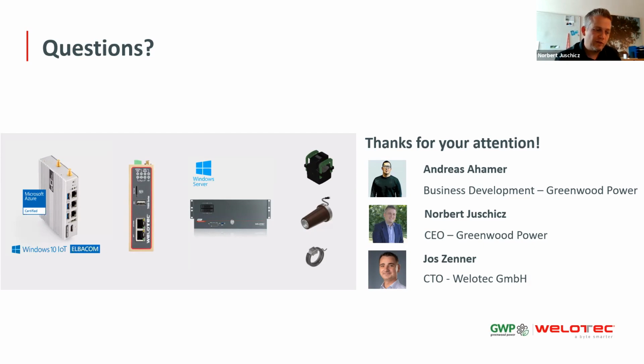If we go down to the low voltage area, it might make more sense, to be honest, because on the low voltage side the biggest use case is load management. In this case, you don't need values every second—every 15 seconds is enough. So it could be sufficient to have just 3 current sensors sending digital data every 15 minutes, and it wouldn't matter if they are synchronized or not. I think it will come, but keep in mind we'd then be talking about active sensors, which means reduced lifetime. This has to be accepted by the end customer, that they'll need to replace these products twice as often as standard sensors on the market. I'm not sure if this will be accepted in the market in the future, but we do see some tendencies in that direction. There is no actual solution in the market at the moment.